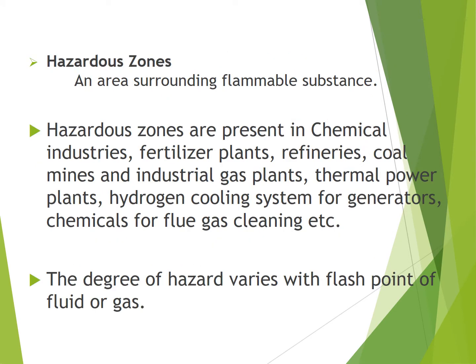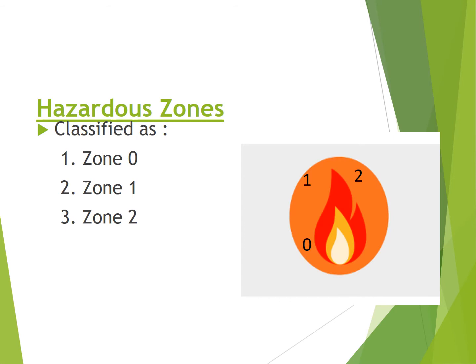Hazardous zones, as I told earlier, are present in chemical industries, fertilizer plants, refineries, maybe in mines, industrial gas plants, and thermal power plants. Thermal power plants use hydrogen for the cooling system of generators. Hydrogen is a flammable gas. Sometimes chemical industries use flue gas for cleaning, and this also will be a hazardous zone. We can classify the hazardous zone into three categories: zone 0, zone 1, and zone 2.